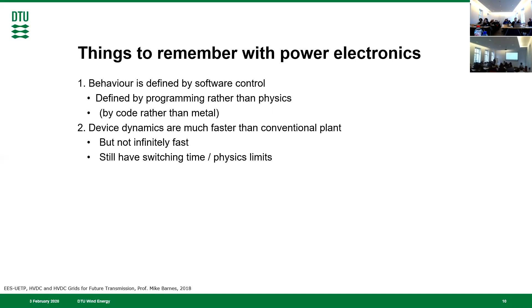The device dynamics are much faster than a conventional power plant. As I said, they switch very fast, but not infinitely fast—they still have some switching time and physics limits. Also, one of the main design drivers of their control and protection is that they are very small devices with very low thermal mass, so they don't like current overload—they heat up very quickly. A lot of the control philosophy is designed to avoid overcurrents, and to some extent voltage overload, but current overload is very important.